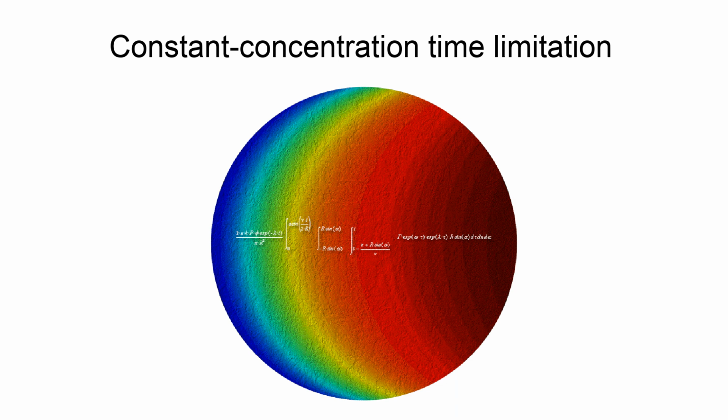Since concentrations resulting from physical events tend to vary with time, due to dilution processes and/or a non-constant source term, airborne radioactivity emission rate, it is not realistic to hold the concentration constant for significant lengths of time. Thus, measurement intervals on the order of several hours are not plausible for the purposes of these calculations.